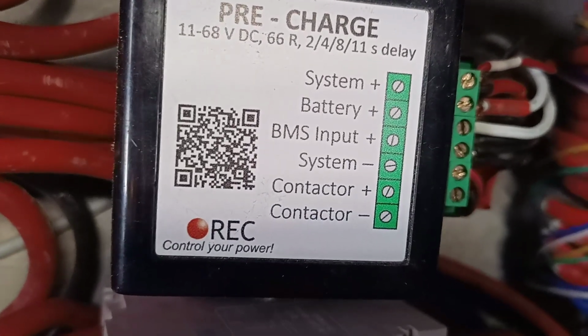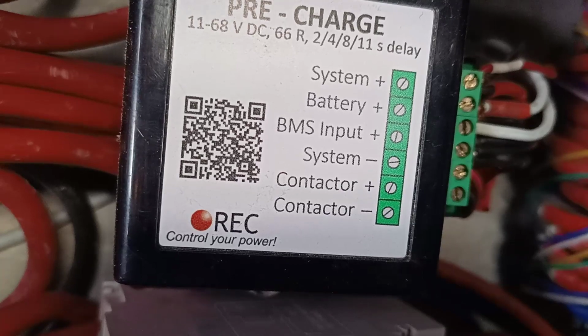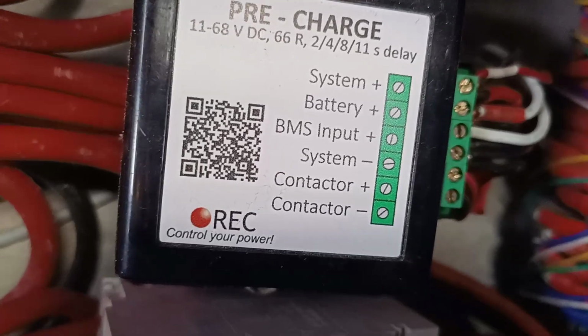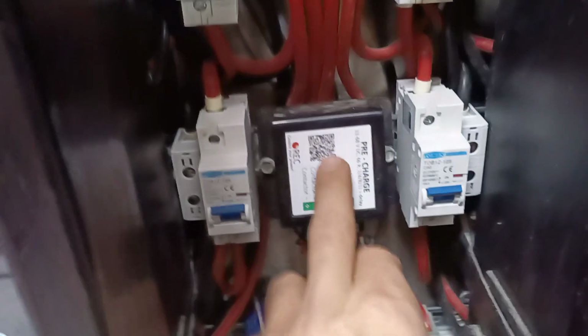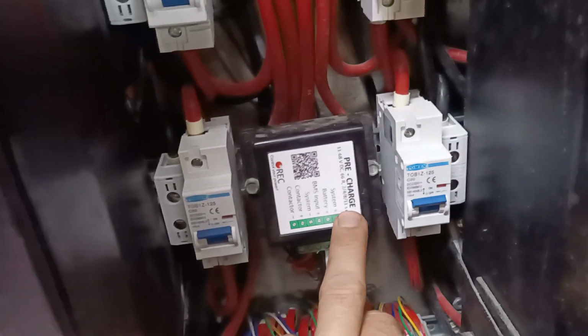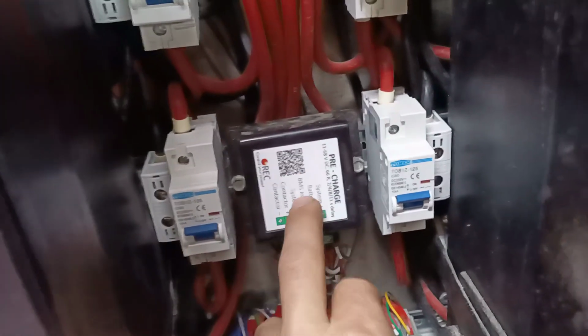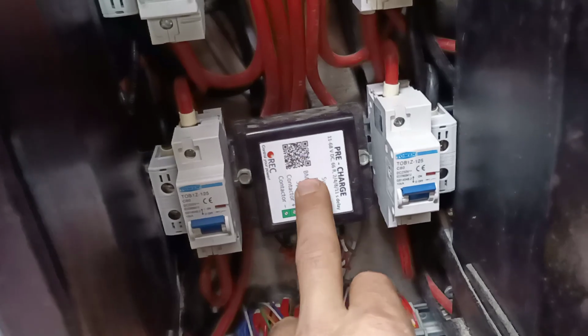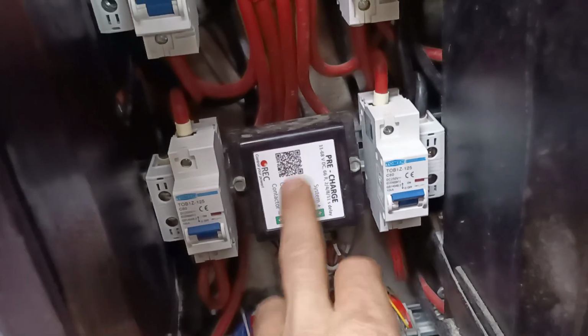As you can see, you can select 2, 4, 8, or 11 seconds pre-charge time, but this pre-charge time doesn't - even if I select 11 seconds, the maximum pre-charge time for this particular unit, the maximum is 6 seconds, and these 6 seconds are not enough to pre-charge my big Sunny Island.